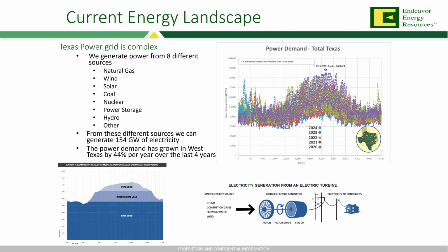That's where natural gas comes in. Natural gas is our pipeline spec, and we open and close that gate as needed to bring on additional power demand. On an average day, we use about 80 gigawatts, with a total capacity across all sources of 154. So we have a lot of room in this grid to bring power on and off, but we have to manage it because it's not just a light switch.